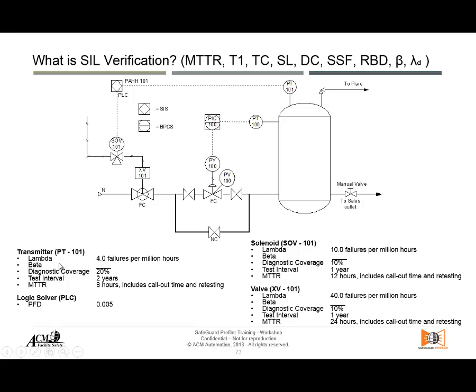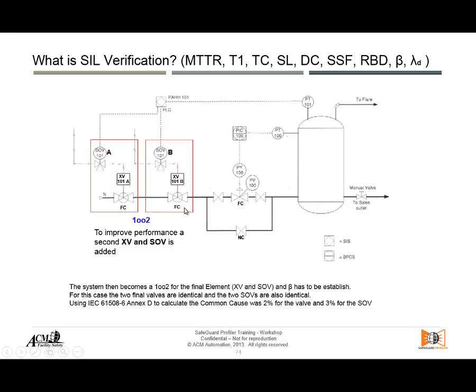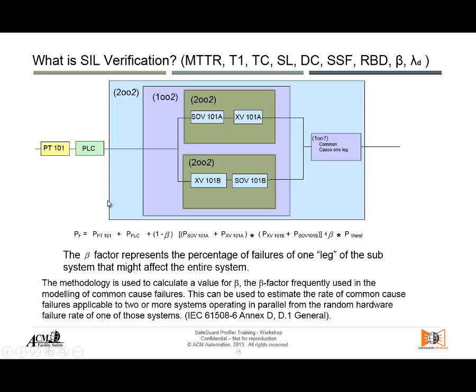Here is an example showing no redundancy versus redundancy on the final element. Remember: solenoid and valve are in a two-out-of-two configuration — both must work. Between set A and set B, as long as one set works, that is a one-out-of-two between the two sets of two-out-of-two solenoid-and-valve combinations. In Safeguard Profiler, if the components are different, we have to build this architecture inside the tool.